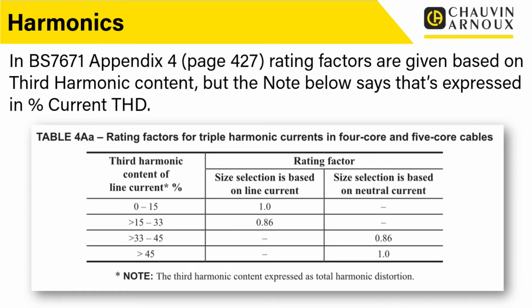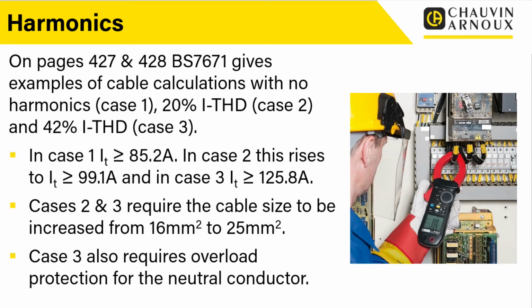So it's great that we've actually got some examples that they've given us. In BS 7671, it gives us examples of cable calculations with no harmonics. That's what they call case 1. 20% current THD, case 2. And 42% current harmonics. That's what they call case 3. And if you actually look at the impact, it's quite a significant impact on the actual tabulated current carrying capacity required for those cables.